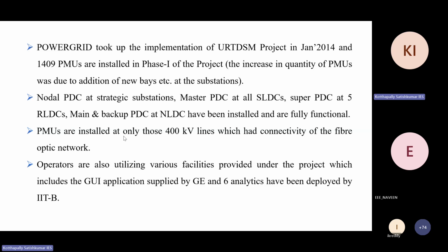So PMUs were installed in phase one only on those 400 kV lines which had fiber connectivity, as I told earlier. Since you have a lot of data, you need analytics to help understand it. Otherwise, if you have raw data of such huge quantity without any analytics, it's not possible to analyze exactly what you want, like voltage contours or frequency contours. For that you need an application. So in phase one, GE developed 6 analytics applications with the help of IIT Bombay, and using these 6 applications you can see the exact data.